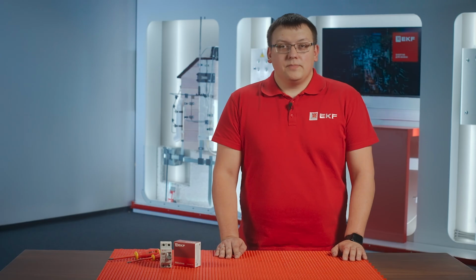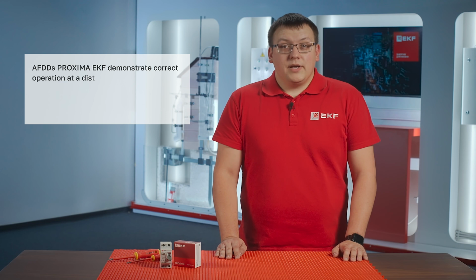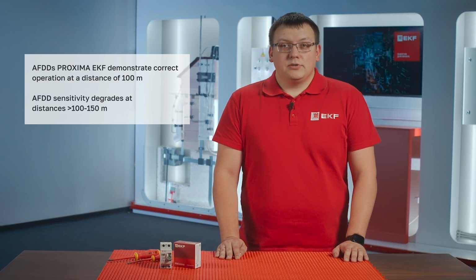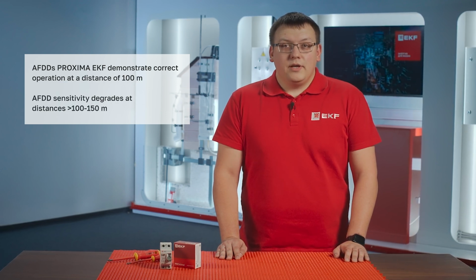In tests, AFDDs made by EKF have demonstrated correct operation at a distance of 100 meters from the source of sparking or from the panel where it is installed. The sensitivity of the AFDD degrades when the sparking occurs at a distance of 150 meters or more. This is due to the physical length of a circuit, which has its own inductance, resistance, and capacitance that together affect the sensitivity of the AFDD.